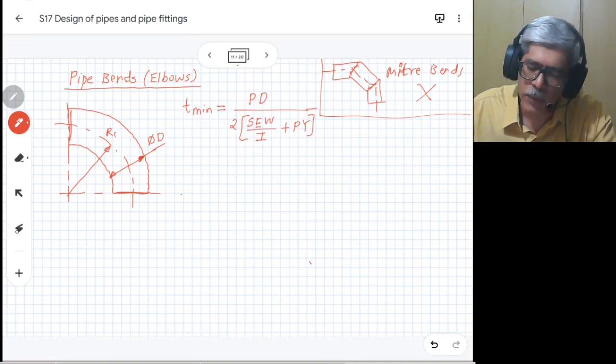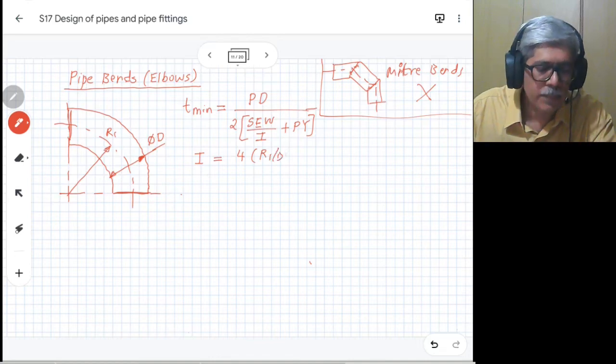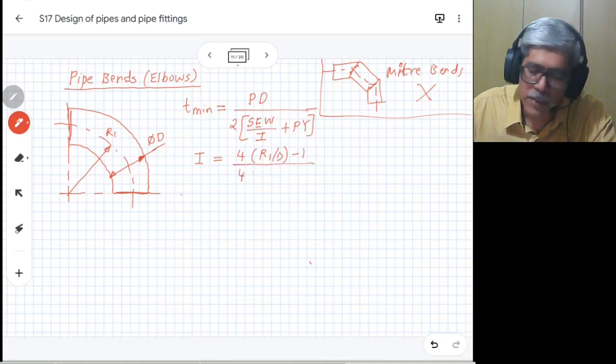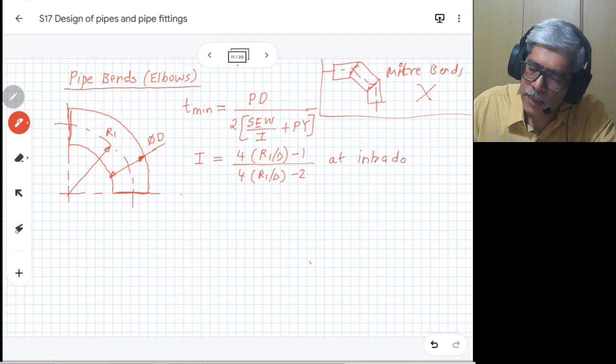The I is the factor which is new. I relates to the bend geometry, so I is given as: 4 times (R1/D - 1) divided by 4 times (R1/D - 2) at intrados.